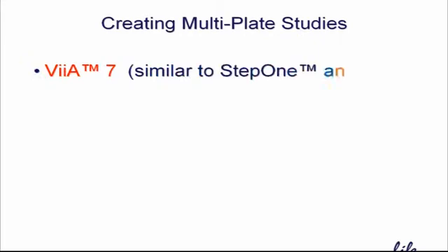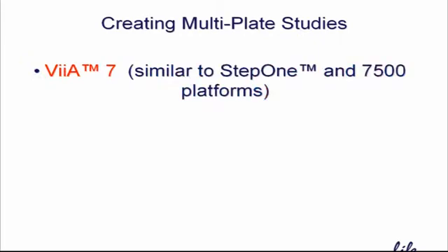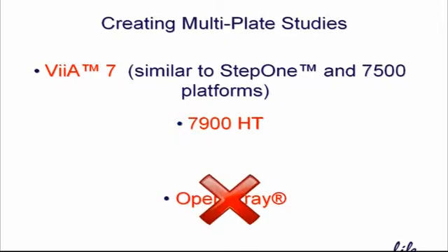Study files ensure that thresholds are equivalent for each assay across every plate in your larger experiment. In this video, we'll see how to create a multi-plate study on the ViiA7, StepOne and 7500 instruments, and on the 7900HT. Note that the BioTrove OpenArray instrument does not require us to take this additional step. We will see toward the end of the video how to export final data out of the OpenArray for use in DataAssist.